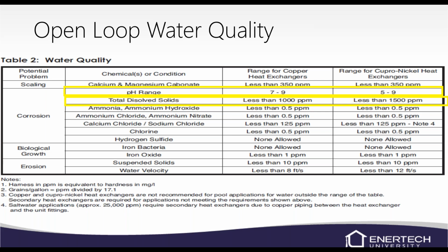So on every job, I would check the water quality. It's really easy to do. If you have bad water quality, it causes the heat exchanger to fail. More than likely, the water is going to enter the refrigerant circuit and the unit's going to be scrapped out. If it's a water quality issue, we can actually void the warranty, and we'd hate to have the homeowner pay for a new unit due to bad water. So before you install the unit, always check water quality, always.